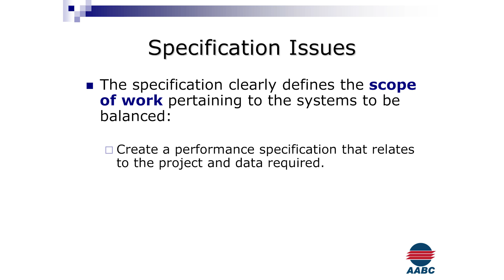The specification should also clearly define the systems we want to get balanced. We have to avoid gray areas, like coming into a hospital where we're only renovating one or two suites and only touching 10 or 12 outlets off a 500-outlet system. What are we really balancing there? Does the owner actually know the implications of balancing this system in the new suites, and what will happen to the rest of the system as we rob Peter to pay Paul?